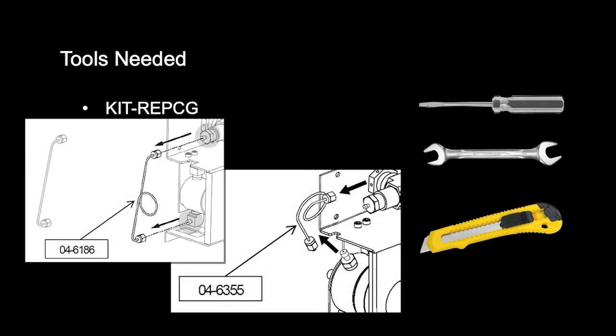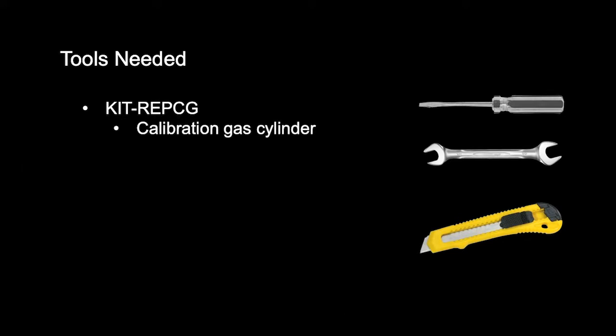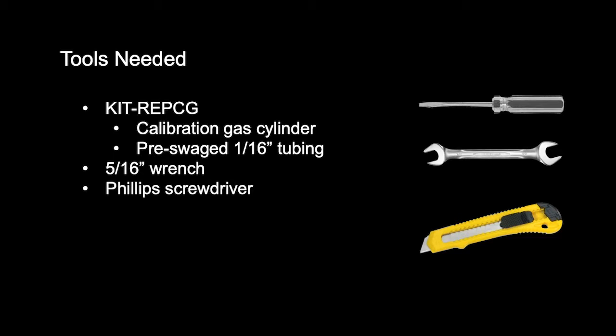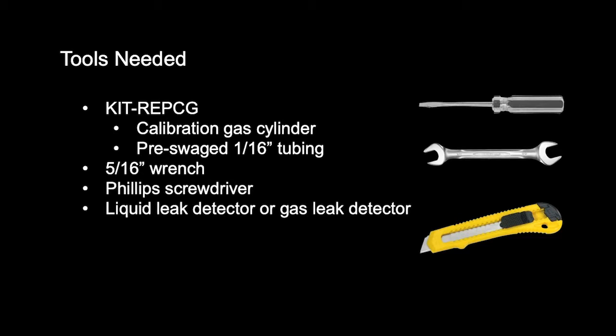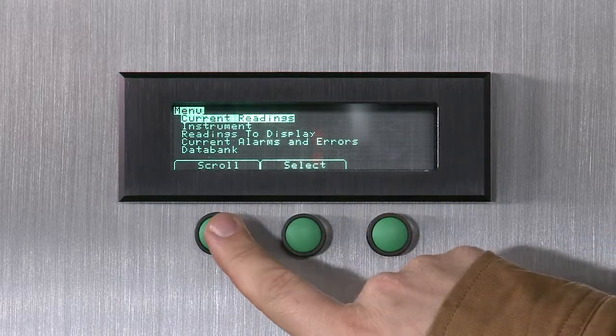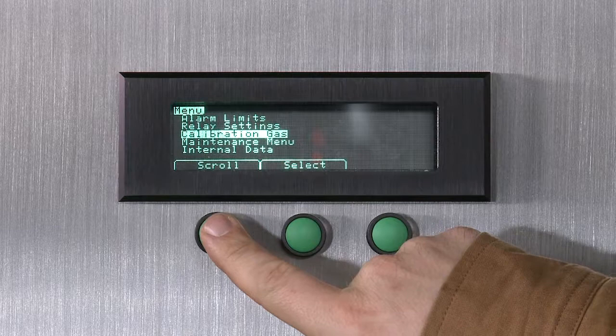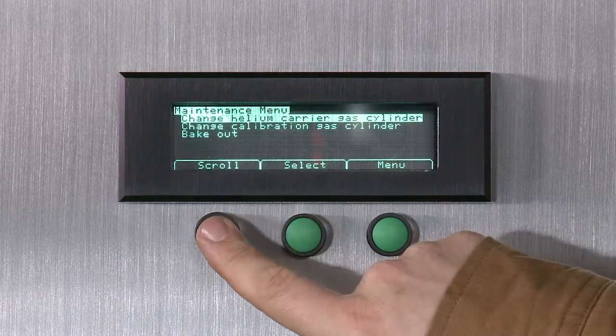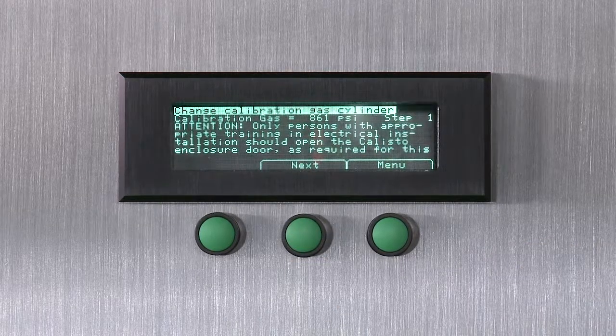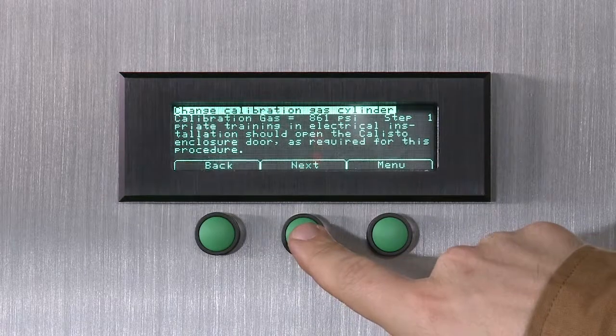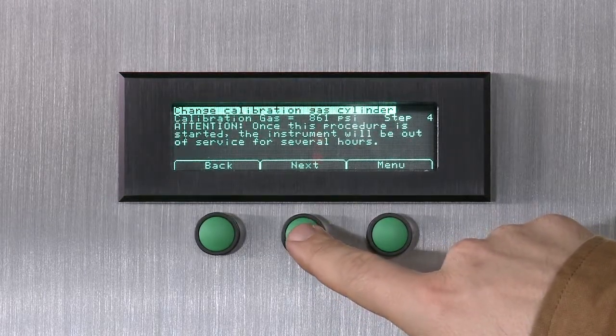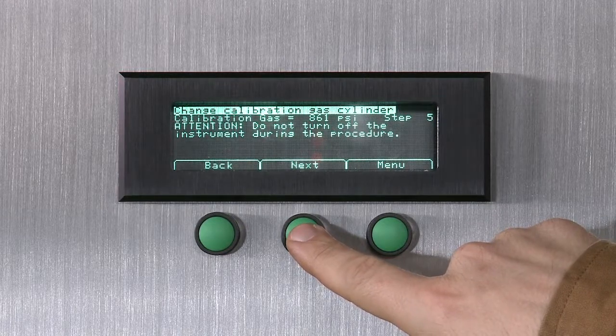Here are the parts needed to replace the calibration gas cylinder. Starting the gas flows. Calibration gas cylinder. On the door of the Calisto, navigate to the Maintenance menu and select Change Calibration Gas Cylinder. Read the on-screen information and press Next for each one. Select Next to begin the procedure.